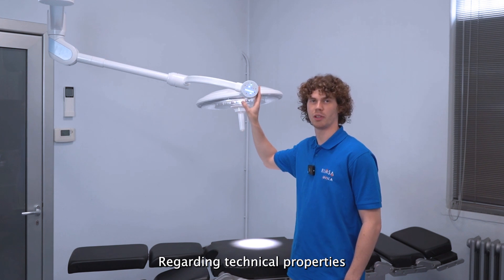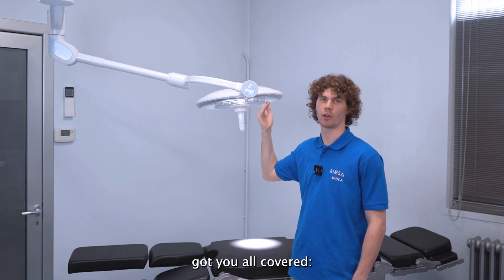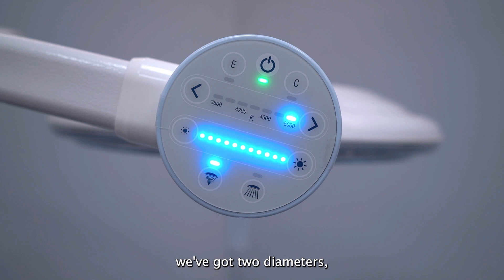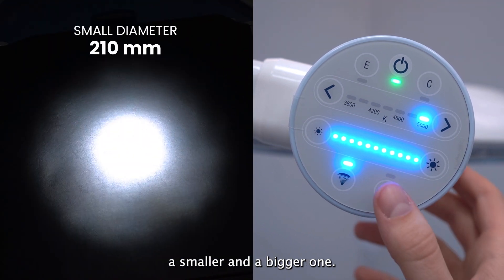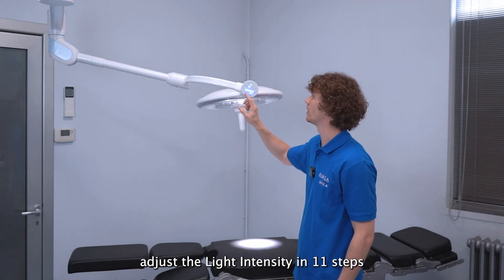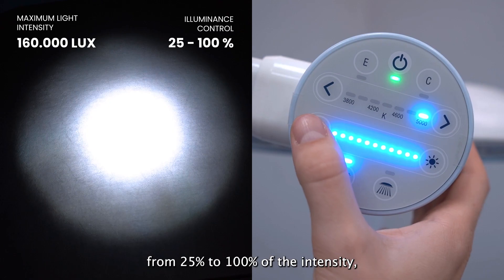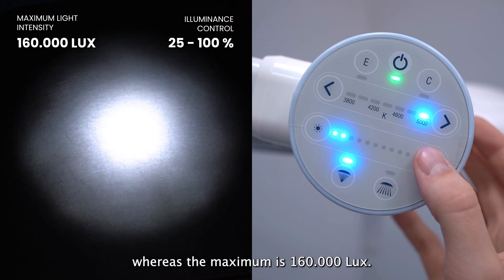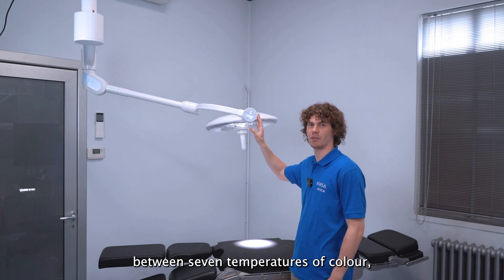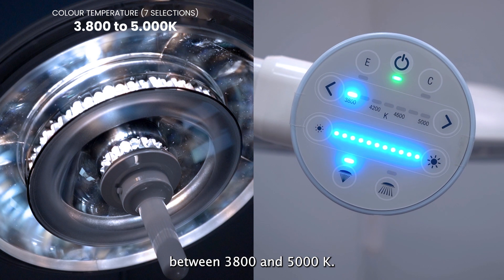Regarding technical properties, Unica covers everything you may need for a surgical lamp. As you can see from the control panel, Unica comes in two diameters — a smaller and a bigger one. You can adjust the light intensity in 11 steps from 25% to 100%, with a maximum of 160,000 lux. You can also choose between seven color temperatures ranging from 3,800K to 5,000K.